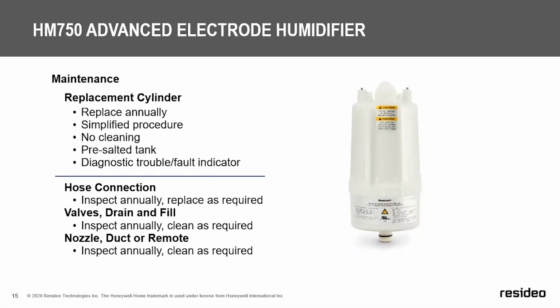Maintenance is pretty simple. Annually, if preferred, or when the diagnostic indicator indicates it's time to replace, which in some applications could be longer than annually, or in high use, high output applications, maybe mid-year or towards the end of a season, the cylinder is replaced. It's a simple procedure where you disconnect the quick connect electrical connections, and then with a screwdriver, you can loosen the clamp on the nozzle connection, or the connection to the nozzle steam hose, and then remove the unit by tipping it back and pulling it out of the solenoid. It doesn't require any cleaning.